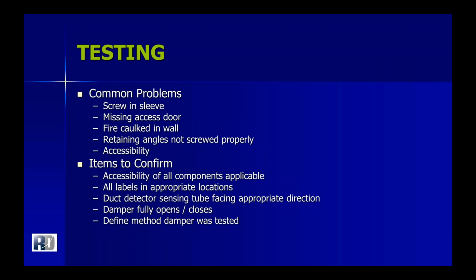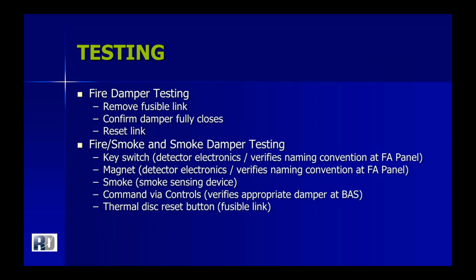All labels: many facilities utilize an asset tagging process, and then there's also your device tag, and many times there's a ceiling grid tag associated with these devices. Is your duct detector sensing tube facing the appropriate direction, as Dave had discussed earlier, or are the openings into the airstream? Does your damper fully open and close? So defining methods of testing, for a fire damper, it can really be as simple as removing a fusible link, confirming the damper fully closes, and resetting the link. So obviously you have to have an access door that's accessible, and then you have to be able to reach through that access door in a safe manner to be able to perform that function.